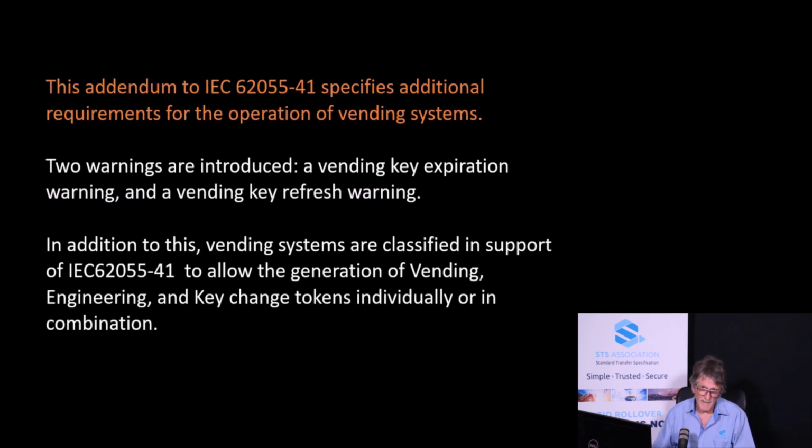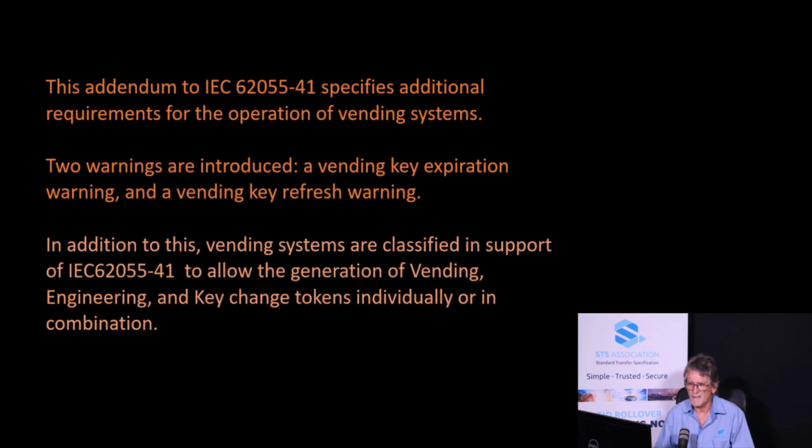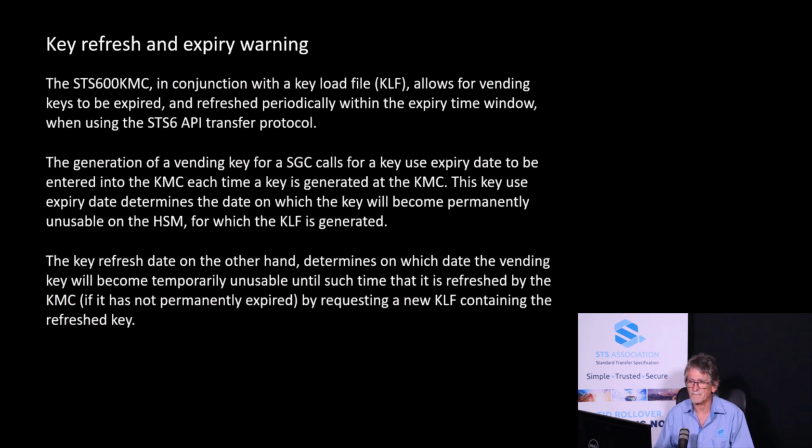This addendum to IEC 62055-41 specifies additional requirements for the operation of vending systems. Two warnings are introduced, a vending key expiration warning and a vending key refresh warning. In addition to this, vending systems are classified in support of IEC 62055-41 to allow the generation of vending, engineering, and key change tokens, individually or in combination.